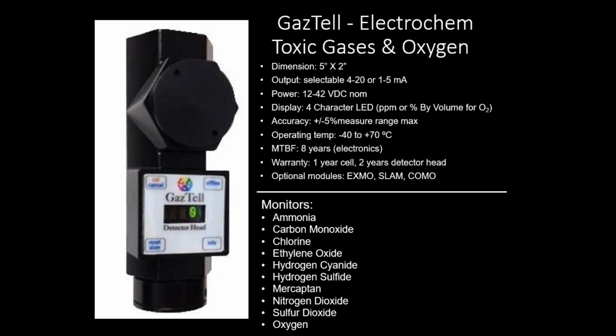Oxygen is the only one that, although we call it a toxic gas detector, is really for oxygen deficiency, and it monitors 0 to 25% by volume, rather than all the other ones on the list there that are part per million sensors. And when we talk about part per million, it's because this GazTell electrochemical detector head is really used for safety. This is not to look for explosions, not to look for high concentrations, not really even intended for leaks. It's intended to monitor so that people are safe in the environment that they're working in.